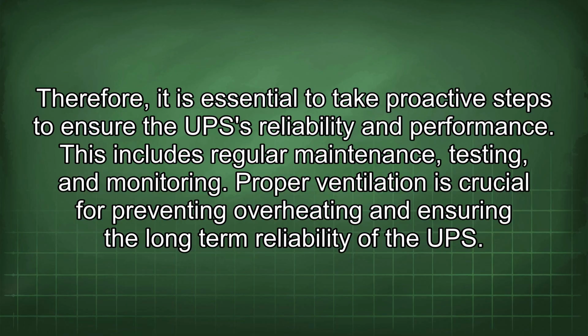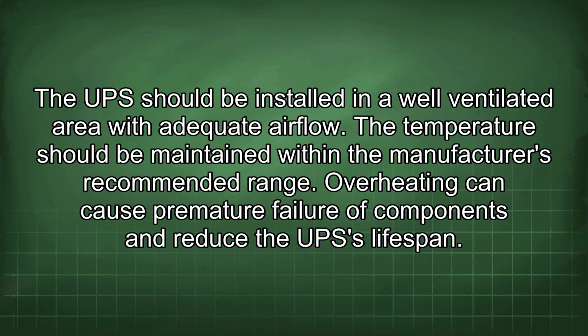Proper ventilation is crucial for preventing overheating and ensuring the long-term reliability of the UPS. The UPS should be installed in a well-ventilated area with adequate airflow. The temperature should be maintained within the manufacturer's recommended range. Overheating can cause premature failure of components and reduce the UPS lifespan.